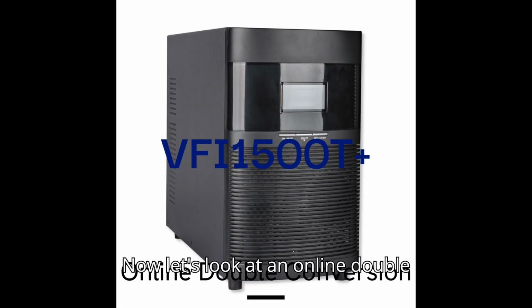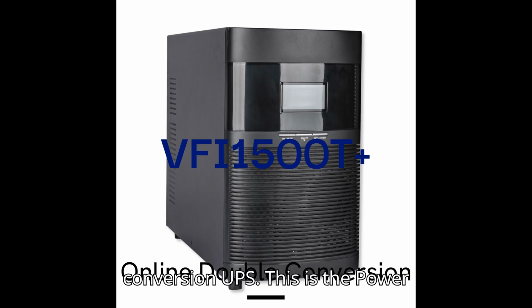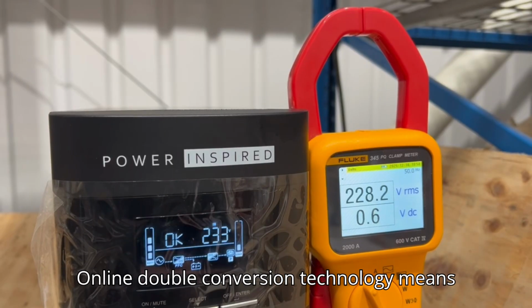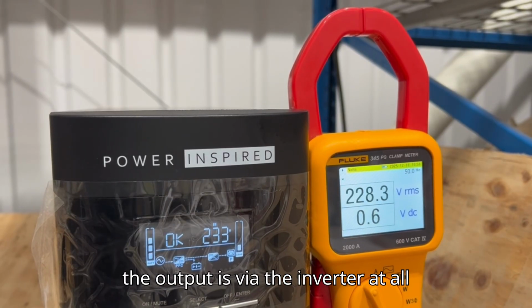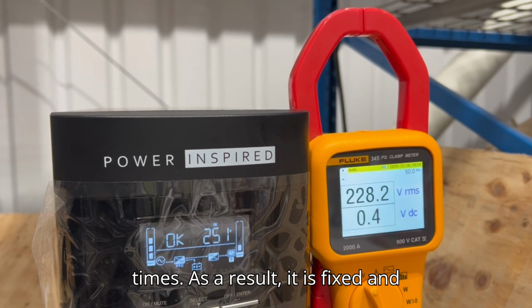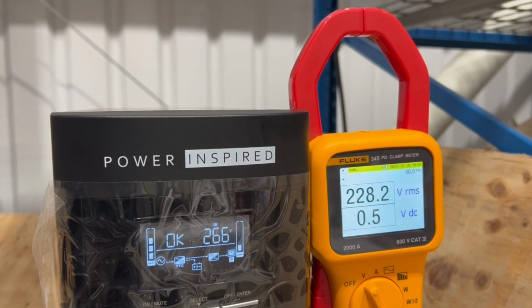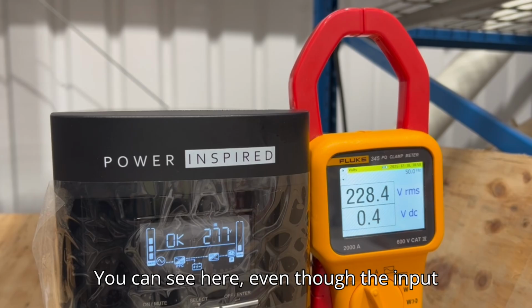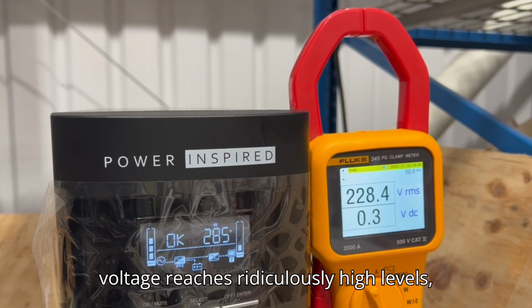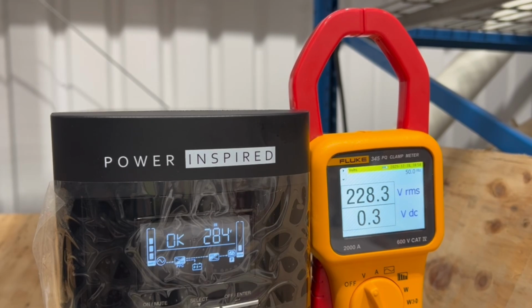Now let's look at an online double conversion UPS. This is the Power Inspired VFI 1500T+. Online double conversion technology means the output is via the inverter at all times. As a result, it is fixed and unwavering. You can see here, even though the input voltage reaches ridiculously high levels, the output is fixed.